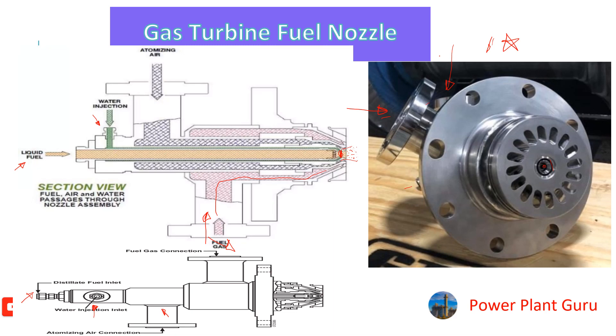Gas is not coming directly like the liquid fuel. There is a swirling action — all the gas nozzles are not straight forward, they have a kind of twist. Each nozzle is angled so that the gas comes in a swirling action.